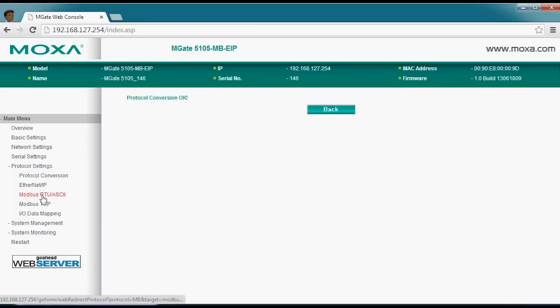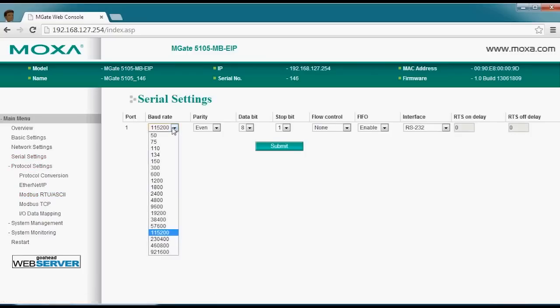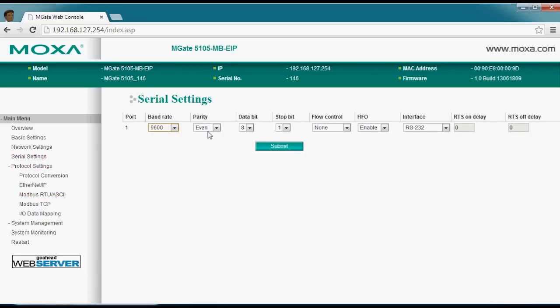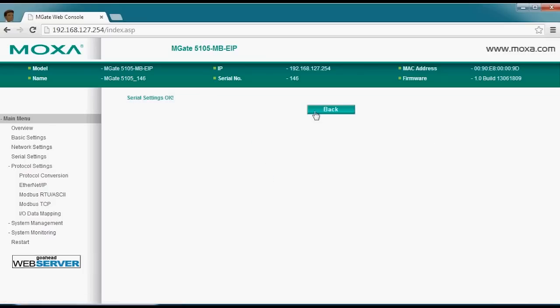Since we've selected a serial connection for the VFD, we need to go in and set the serial port settings. We're going to select 9600 bits per second, keep even parity, eight data bits, one stop bit. We do want to change the interface to RS-485, so let's go ahead and make those changes active.